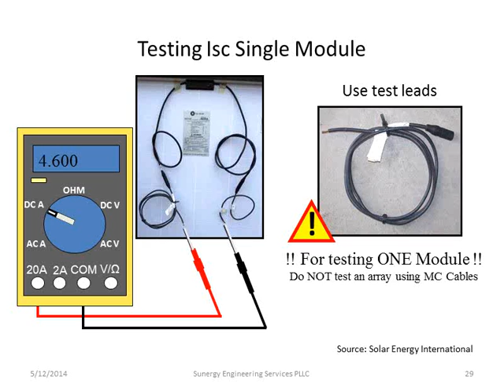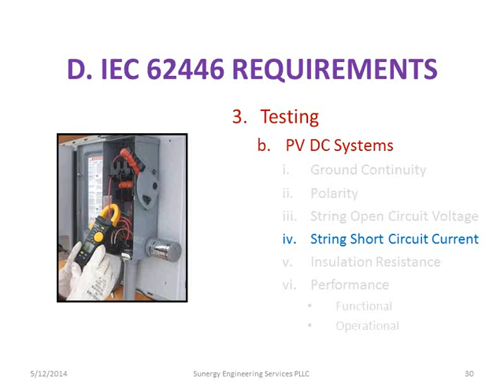But you can't do that with a full string. It's way too much fault energy to do that with a full string. And besides that, your meter is probably not rated to do it either. So the only real way to do that is with a clamp-on meter. That's a safe way to do it when you're doing string measurements. But then it's hard to get the short circuit current. You can get the current going into the inverter quite easily because you can just do it through the wiring system, but the short circuit is a little bit harder. So the tools from Europe have been made specifically to do those tasks, so they do it automatically for you, which is really nice.